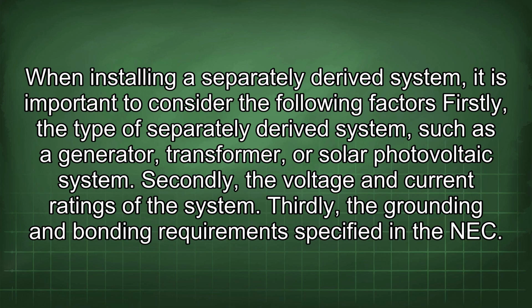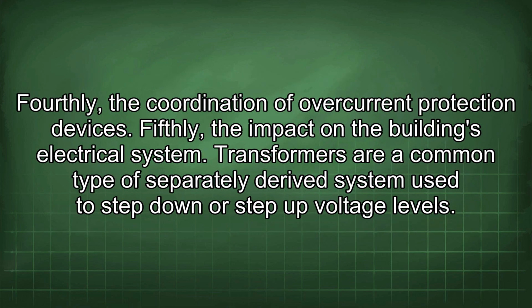When installing a separately derived system, it is important to consider the following factors. Firstly, the type of separately derived system, such as a generator, transformer, or solar photovoltaic system. Secondly, the voltage and current ratings of the system. Thirdly, the grounding and bonding requirements specified in the NEC. Fourthly, the coordination of overcurrent protection devices. Fifthly, the impact on the building's electrical system.